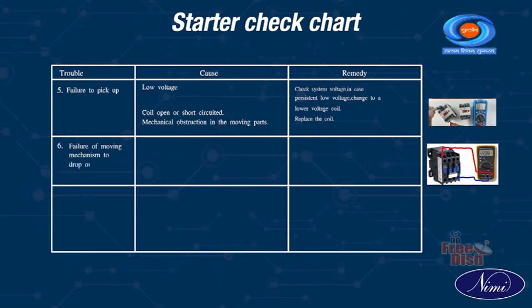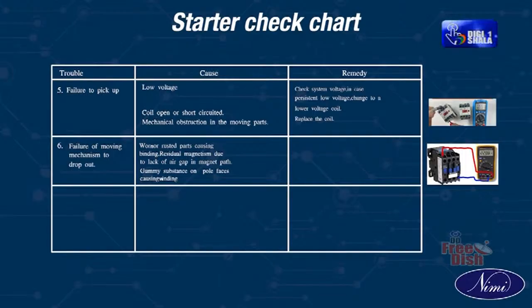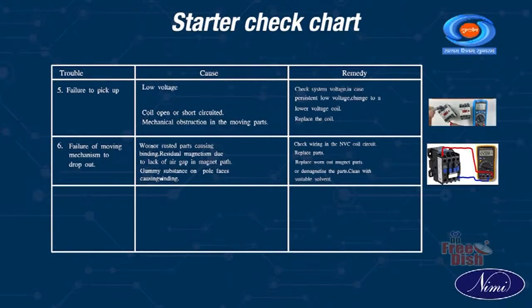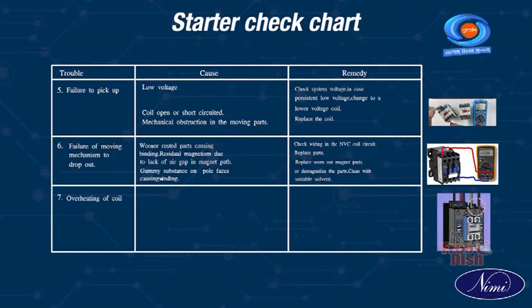Trouble. 6. Failure of moving mechanism to drop out. Cause. Worn or rusted parts causing binding, residual magnetism due to lack of air gap in magnet path, gummy substance on pole faces causing binding. Remedy. Check wiring in the NVC coil circuit. Replace parts. Replace worn out magnets or demagnetize the parts. Clean with suitable solvent. Trouble.